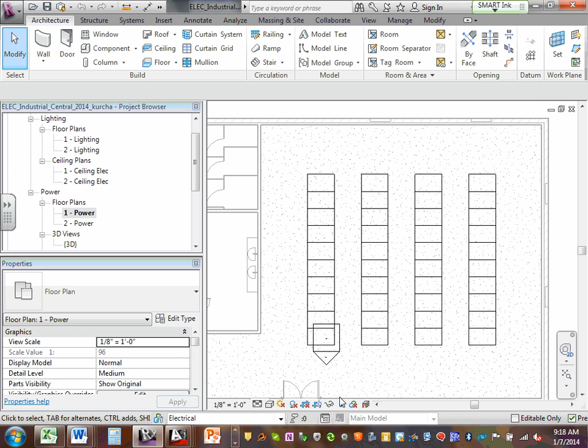At each rack, we're going to be providing two 208 volt 30 amp feeds to each server cabinet. There's going to be a plug. They're usually twist locks. You've got your regular plugs that are just straight blade, they plug in, and then they also make a locking receptacle that plugs in and then twists. So once it twists, you could put your foot on the cord and it won't come out. It's a little bit more secure when they're locked in. Because the last thing you want to do is spend $20 million on a UPS system for redundancy and have somebody just unplug it out of the wall.